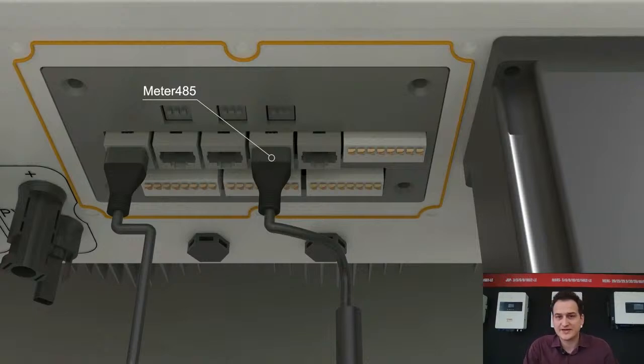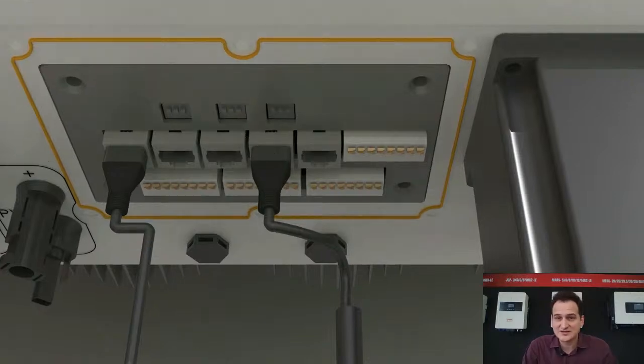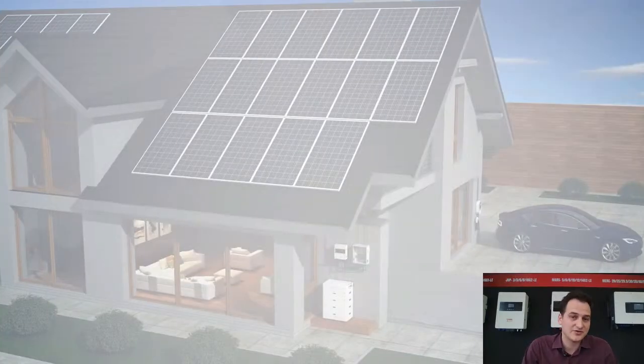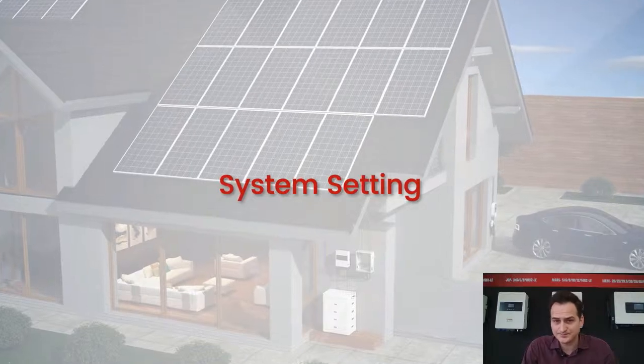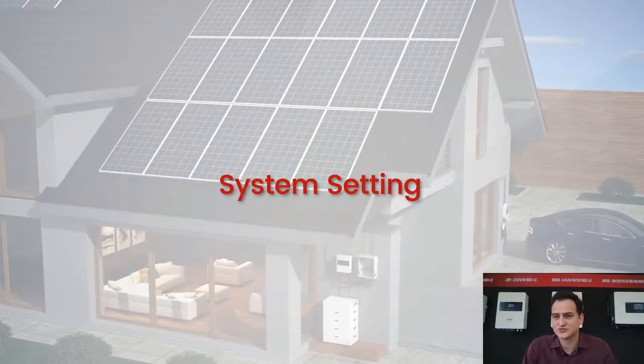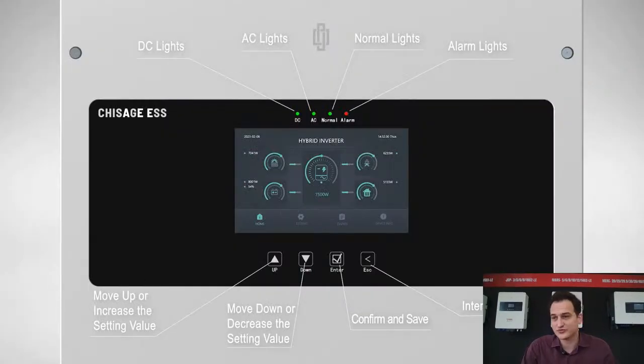We use pins 7 and 8 of the Ethernet cable, or we can also put this on the 7 and 8 port. So you can find the 7 and 8 numbers on these pins on the right and connect our meter communication cable here. And the inverter is wired, and now we can go to settings.